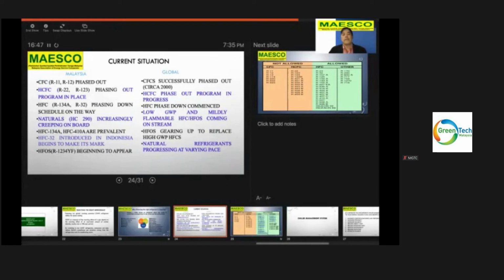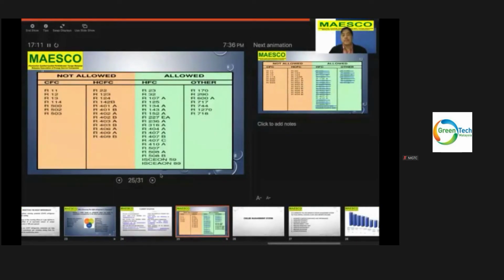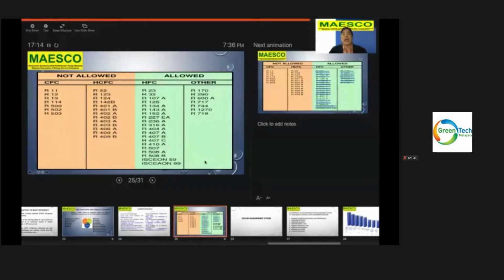Natural hydrocarbon R290 is increasingly creeping on board. Currently, we are using a lot of HFC R134a, and HFC R410A is prevalent. So do catch up with the current situation and know what refrigerant can be used and what cannot be used. Now this is all I've listed down, the refrigerants allowed and not allowed. So do take note of which are allowed and which are not allowed.